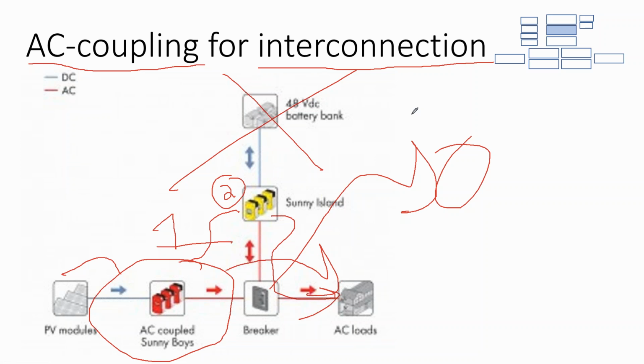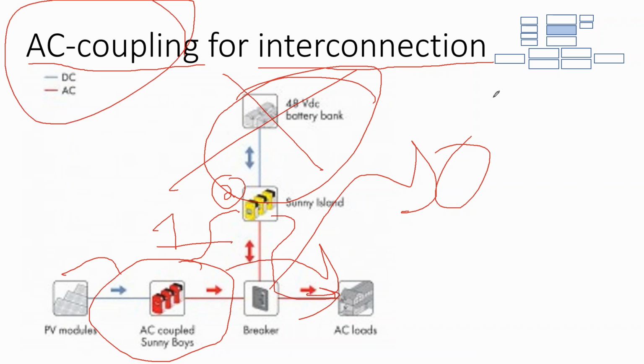And so when you look at utility scale projects and utility scale batteries, those batteries are commonly AC coupled, because primarily they're not using the batteries to supply the load. Primarily, they're using the grid or the solar array to supply the load and not the batteries themselves. The batteries are only being used for a few hours a day, a few hours a week, or a few hours a month. So when you're not using the batteries for the bulk majority of the day, AC coupling is the better way to go.